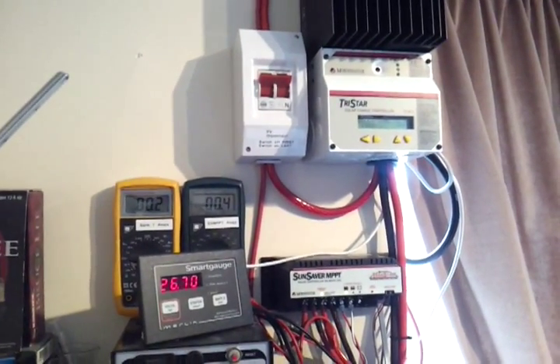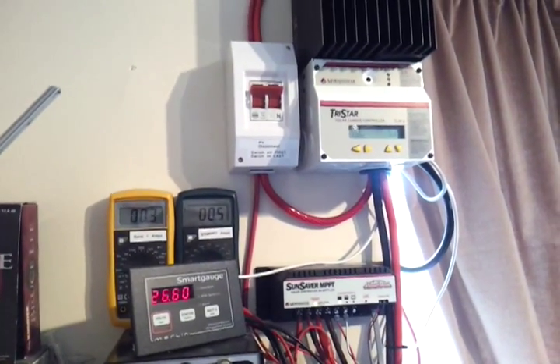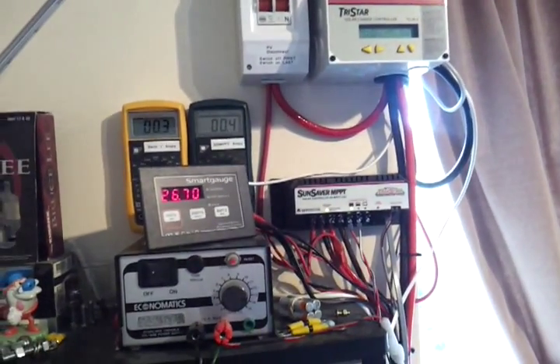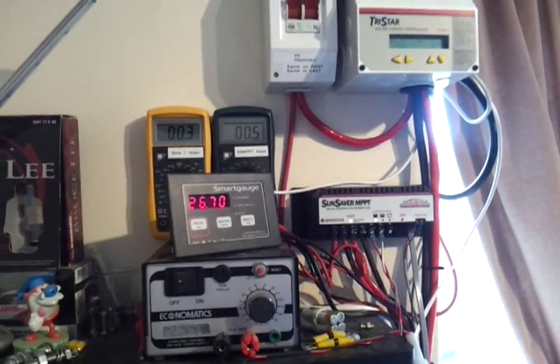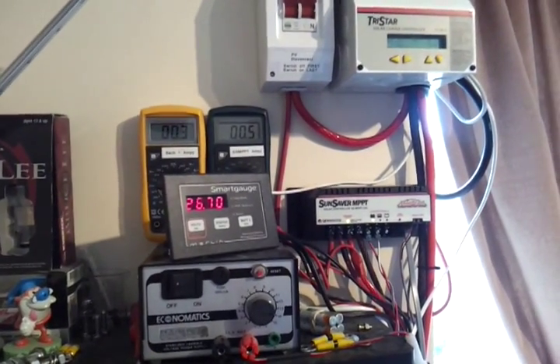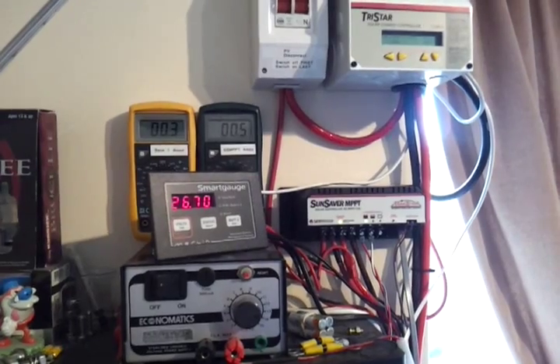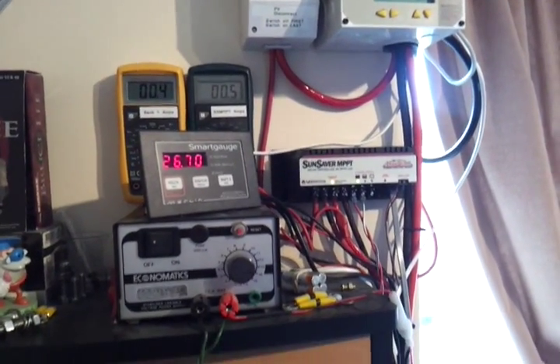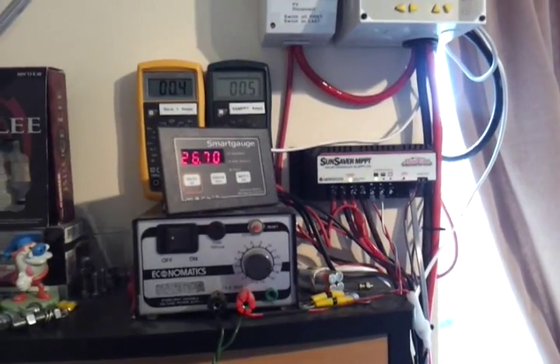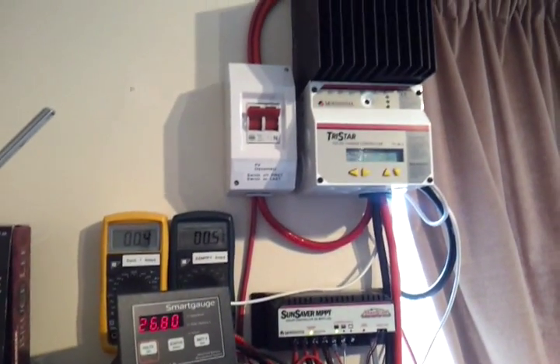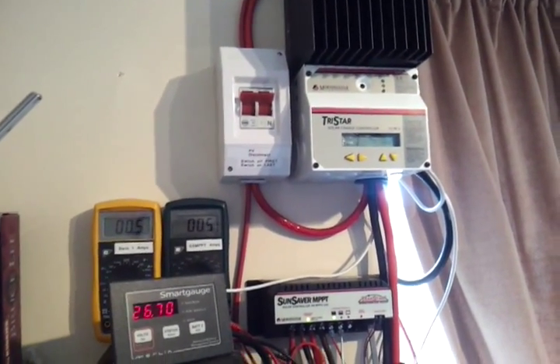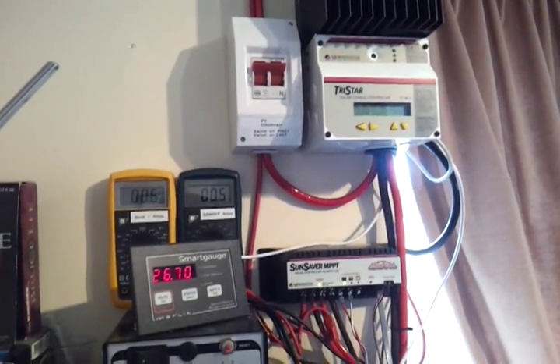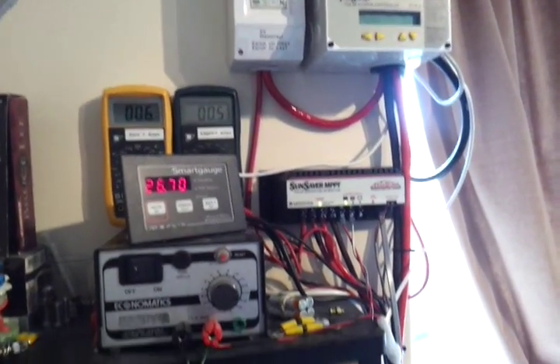I've set the nominal charging voltage maximum to 3.5 volts per cell. It's quite low but quite safe, and it will only sit at its absorption voltage of 3.5 volts per cell for 10 minutes before dropping down to the float voltage.